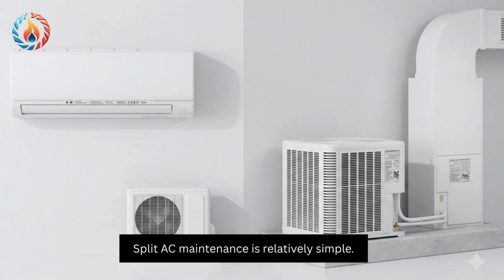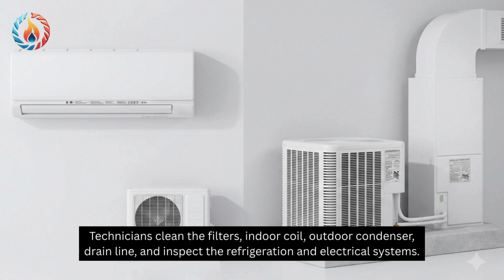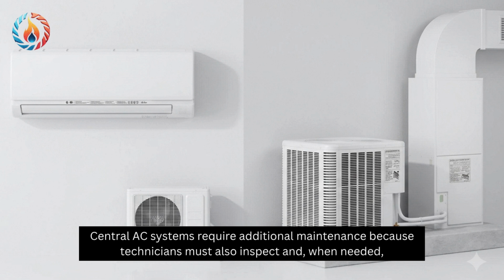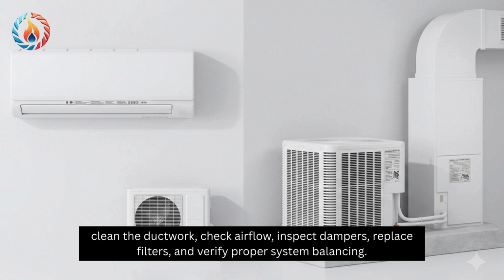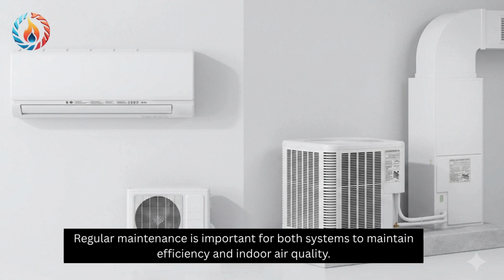Maintenance. Split AC maintenance is relatively simple. Technicians clean the filters, indoor coil, outdoor condenser, drain line, and inspect the refrigeration and electrical systems. Central AC systems require additional maintenance because technicians must also inspect, and when needed, clean the ductwork, check airflow, inspect dampers, replace filters, and verify proper system balancing. Regular maintenance is important for both systems to maintain efficiency and indoor air quality.